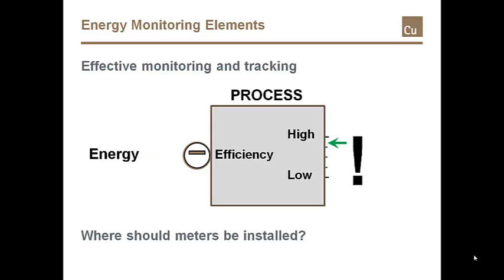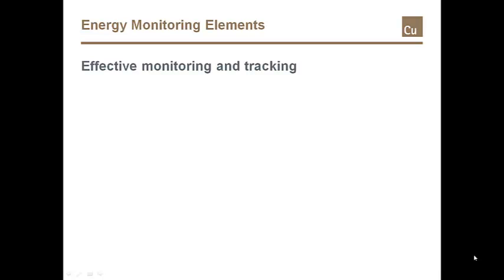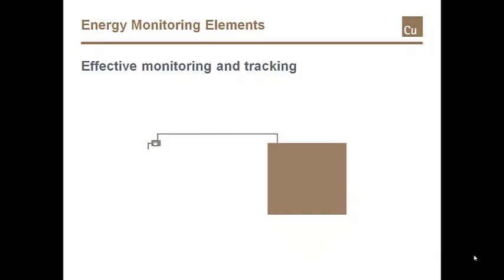Which processes should require metering? Those using significant amounts of energy, or SEUs, such as heat processes and large numbers of compressors or chillers. While not a process, large numbers of high wattage light fixtures may consume significant energy in the facility and may merit tracking as well. For ISO 50001, effective monitoring and tracking begins with a defined scope and boundary.